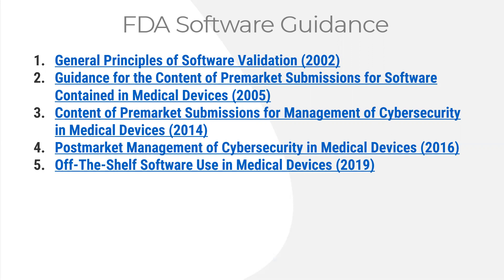The third guidance document is the Content of Pre-Market Submissions for Management of Cybersecurity in Medical Devices, a 2014 document. The FDA created it because they felt IEC 62304 didn't provide enough detail on cybersecurity. The US FDA went above and beyond in their cybersecurity expectations back in 2014, and now the rest of the world is catching up. The FDA was really leading on what should be done for cybersecurity of software embedded in medical devices and for standalone software as a medical device.